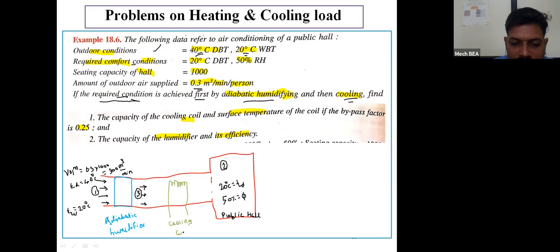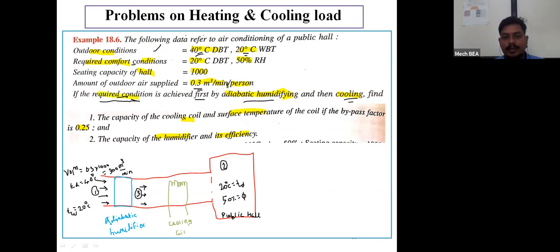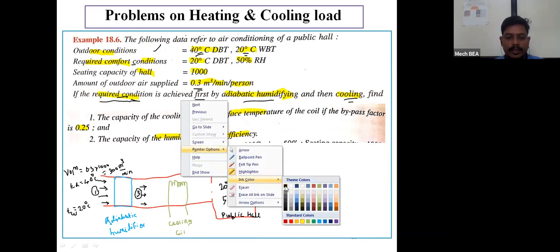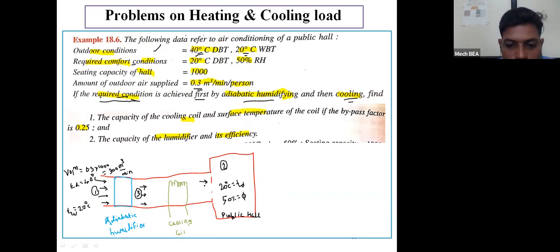And as they have not provided the load which is being generated inside the room, they have directly mentioned that the required condition is achieved. The required condition is directly achieved by adiabatic humidifying and then by cooling. That's why this will be my point number 3. After passing air with the condition of point number 3 over this cooling coil, whatever supply air will be generated, after passing that supply air to the public hall, I can get this required condition.